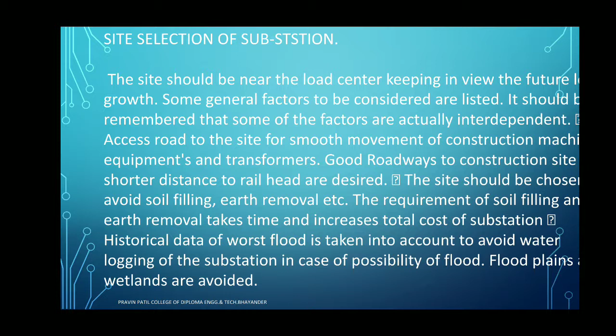We have to see another point of site selection for an electrical substation. First, atmospheric condition is also essential, like salt and suspended chemical contaminants. We have to avoid that area, considering selection of equipment and maintenance requirements. We have to avoid the salt area and suspended chemical contaminant zone, and select the proper area.